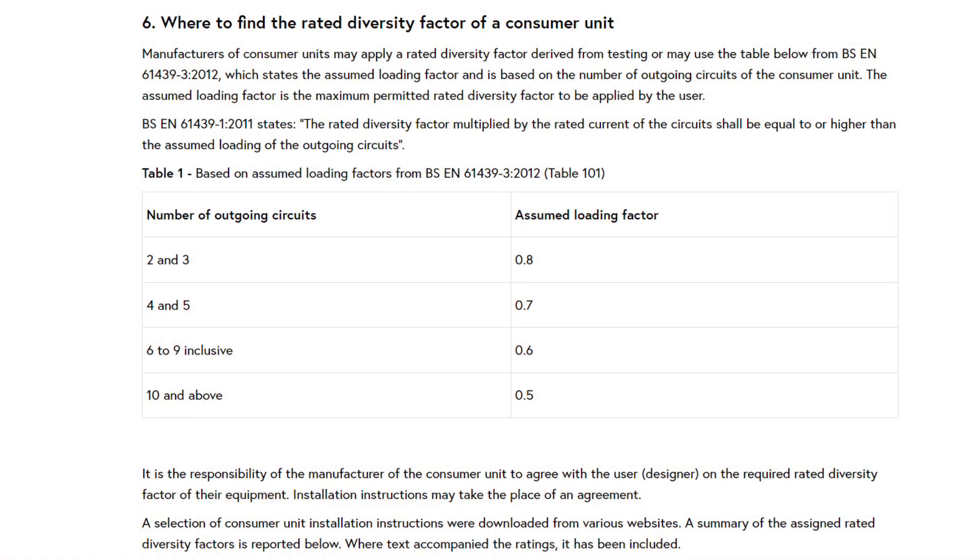In BSEN 61439-3 we find a table of assumed loading factors that can be used as the rated diversity factor of the protective device. Many brands will have their own data and variations on these figures, and for the most up-to-date information you should always consult the manufacturer's data. But many brands, Lewden included, use this table as the standard reference.